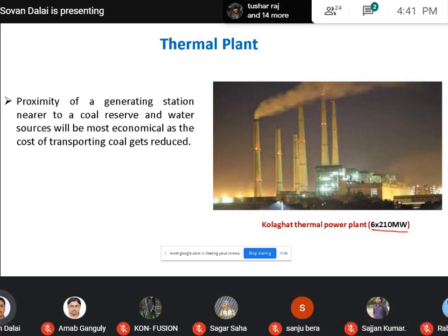Now this is the requirement of a thermal power plant: the generating station should be near the coal reserve and the water source, so that it is economical. But this is not always true, or we do not always maintain that the thermal power plant should be near the colliery or the water source. It is not always possible, but if it is possible to build a power station near the coal reserve or the water source, that will be beneficial from the cost point of view.